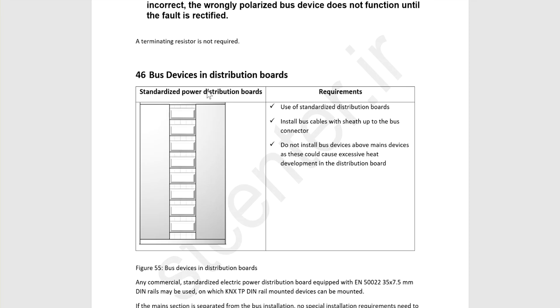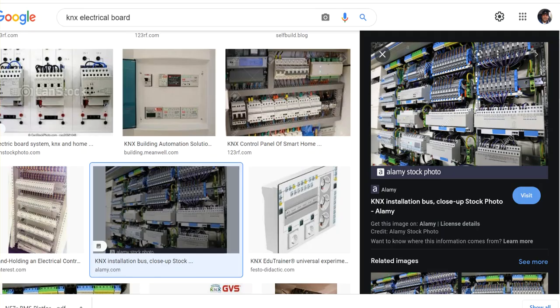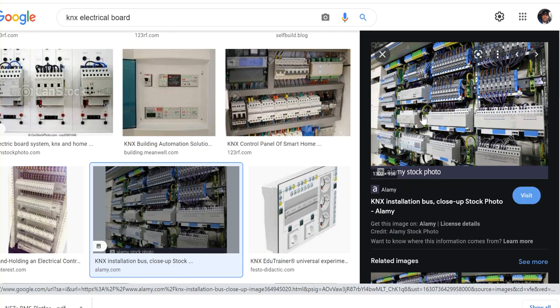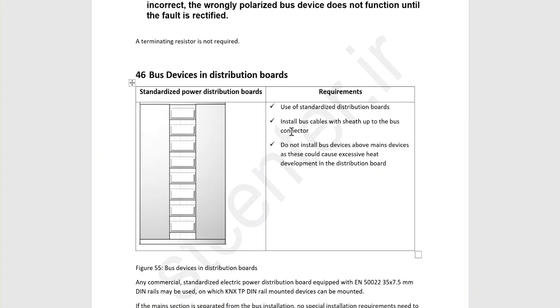Okay, about the bus devices in the distribution board. The book talks about the electrical board or distribution board and the concerns. The distribution board is used to place the relay actuators, dimmer, mini server, and many other things that we need in a KNX TP installation. And the book says there are some concerns about it. So what are the concerns? We should use a standard distribution board. It means we cannot use a board made of wood or some low quality plastics. We should always use the standard type.